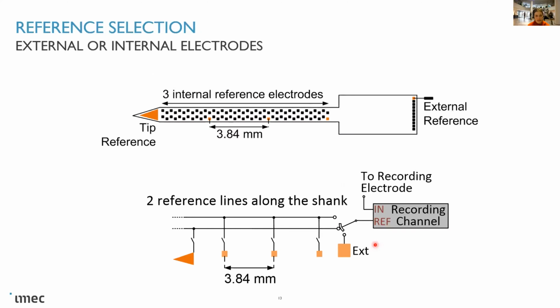We also have the options for reference selection. Referencing is very important for the experiments that you want to do, because this will also determine the signal to noise ratio, and it will determine a lot how much noise or how many artifacts you get. So basically we have 3 options here. The probes include a very large tip electrode that can be used as a reference. We have a few small electrodes as well that can be selected. However, since these electrodes are very high impedance, the cancellation is not super great if you want to use only one electrode as reference for all the channels. It's very high impedance to drive too many channels at the same time.